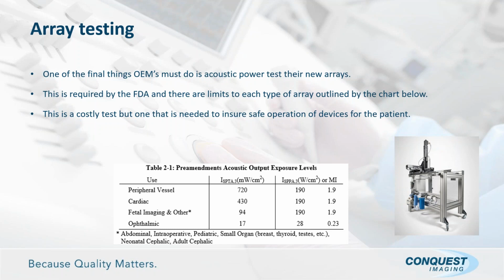Now, one of the things that you may or may not be aware of, but again, this is a cost, and this is an expensive cost, is once an array is designed and finalized and manufactured, one of the final things the OEM has to do is get it acoustic power tested. There is a requirement by the FDA, and I attached the chart right out of the FDA guidelines, that depending on what the array is used for, vascular, cardiac, fetal, which includes abdominal and so on, these acoustic output levels are set for the FDA by the American Institute of Ultrasound in Medicine and others. And as long as the OEM's new array meets these levels, that's fine, but they can't exceed them.